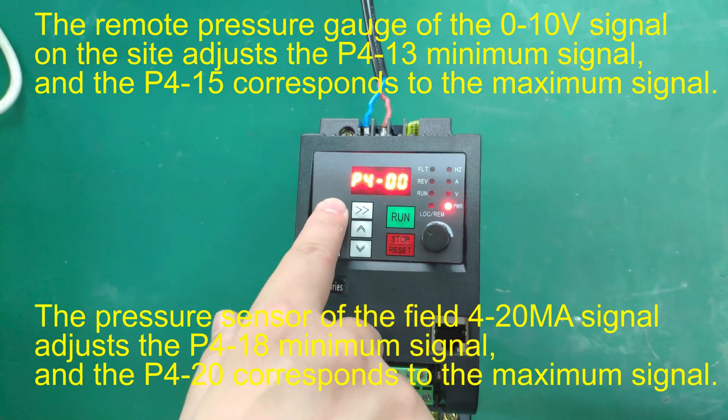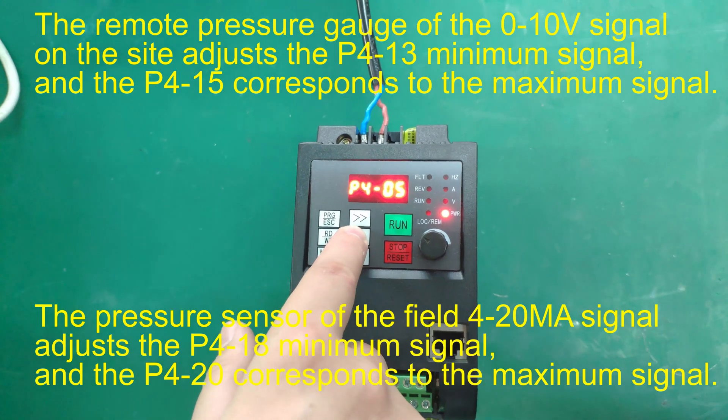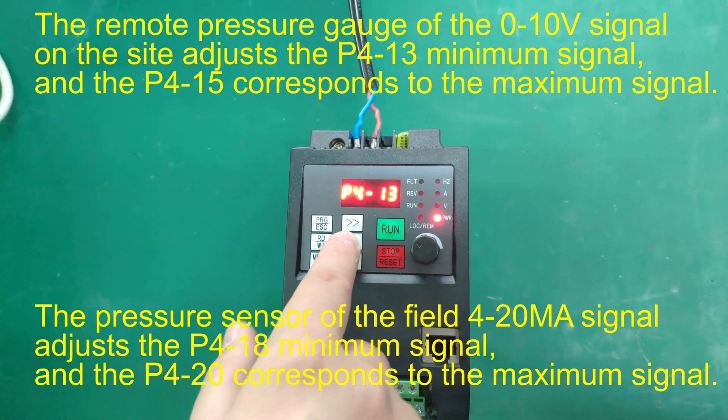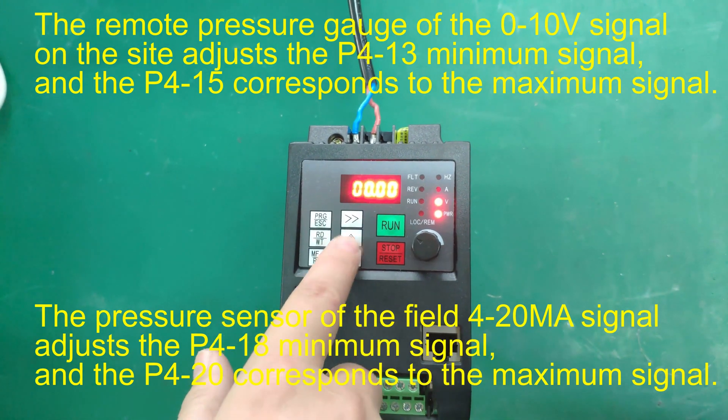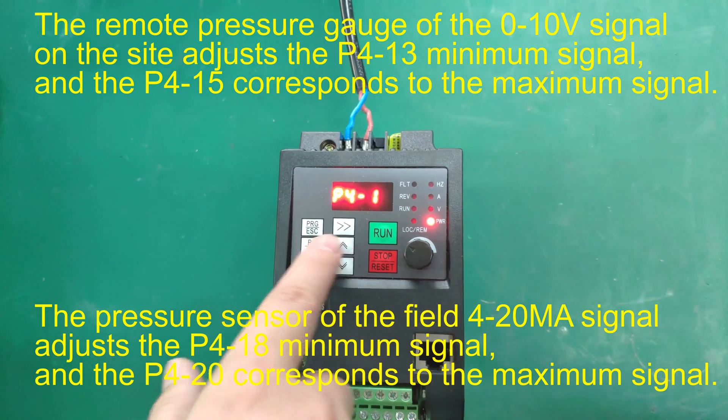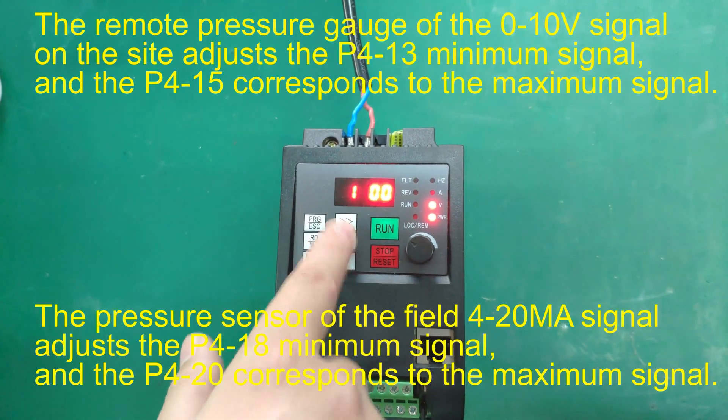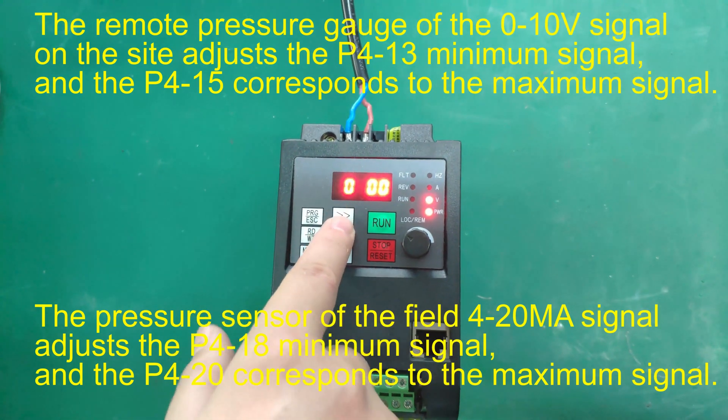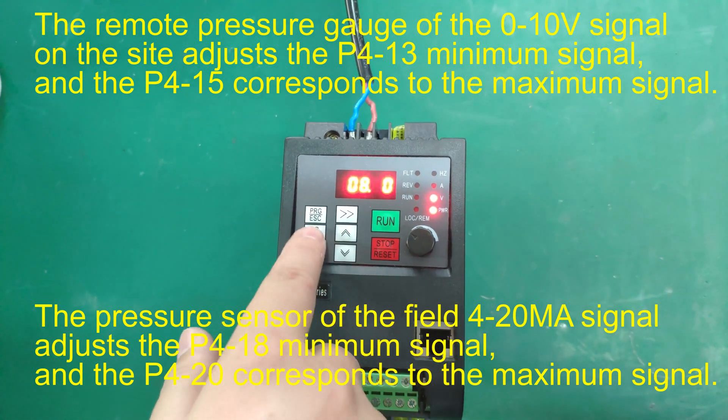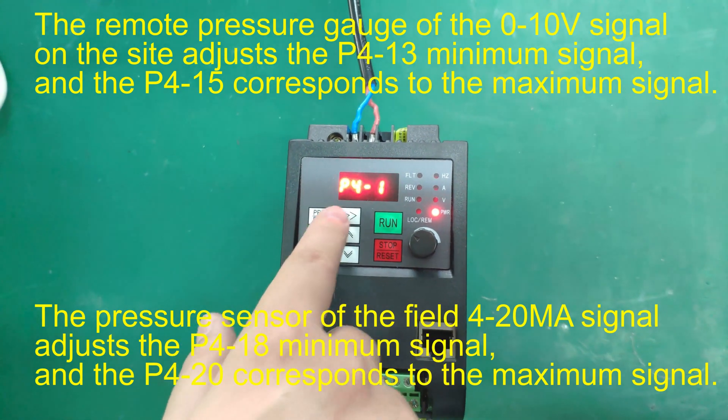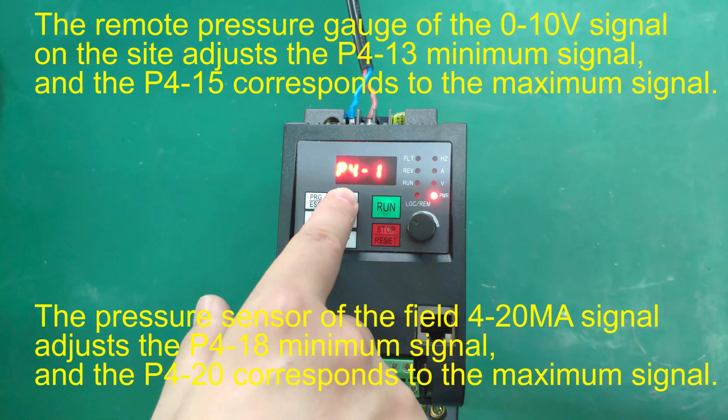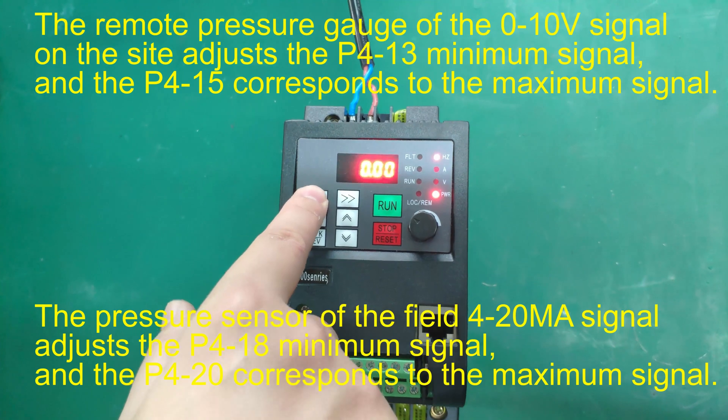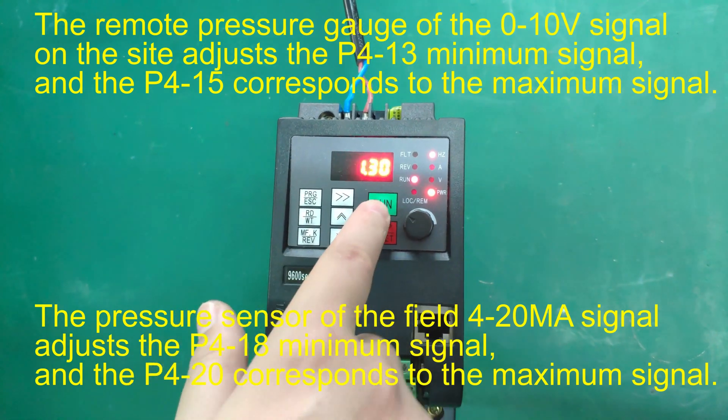The remote pressure gauge of the 0-10V signal on the site adjusts the P4-13 minimum signal, and the P4-15 corresponds to the maximum signal. The pressure sensor of the field 4-20MA signal adjusts the P4-18 minimum signal, and the P4-20 corresponds to the maximum signal.